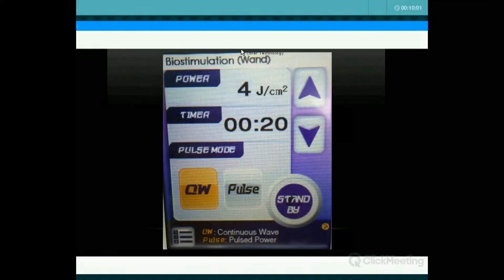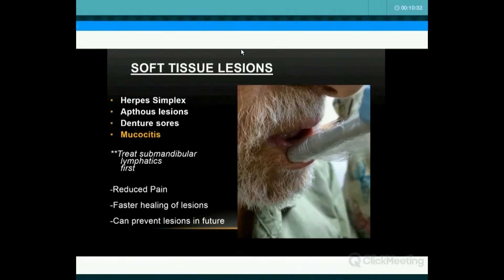The device settings are preset — it tells you what to do. With either of the tips, it's going to give you four joules in 20 seconds. It doesn't matter which of the two tips you use. Because it's joules per centimeter squared, a one-by-four centimeter wand tip needs a lot more energy than a three millimeter tip, but since it's factory preset, both will take 20 seconds. The bioinhibition setting takes 40 seconds and delivers eight joules per centimeter squared.